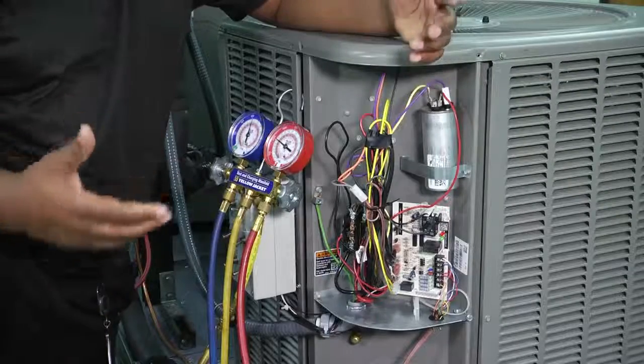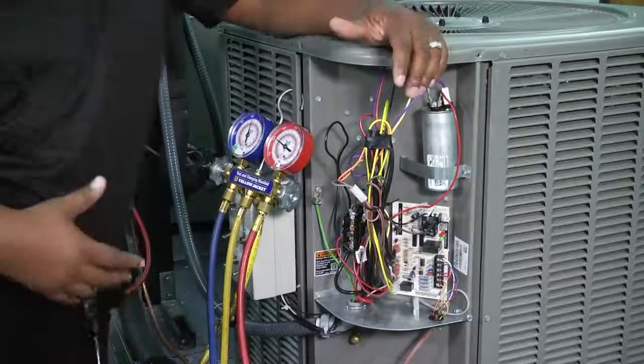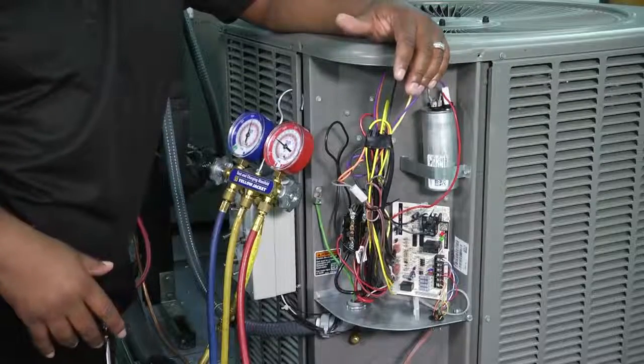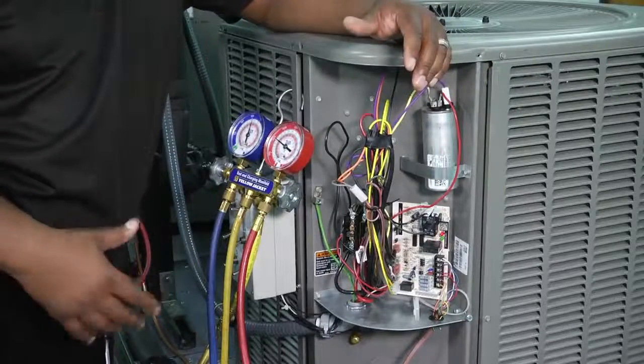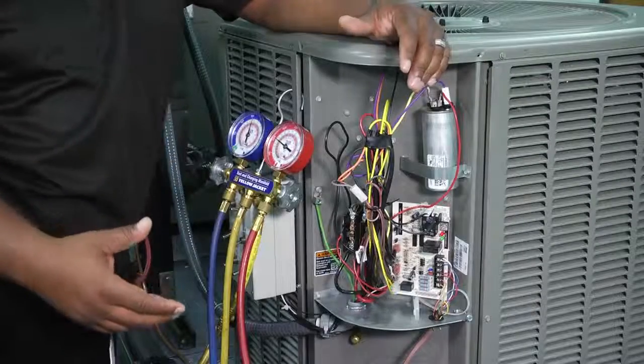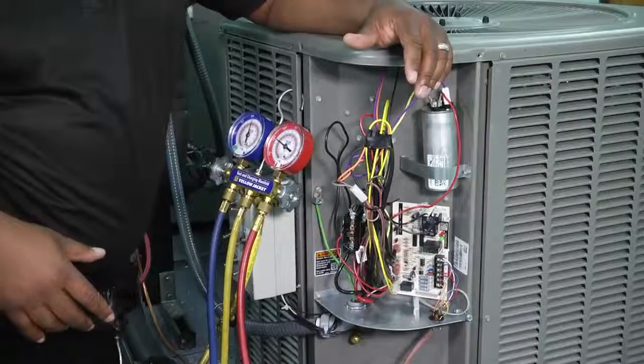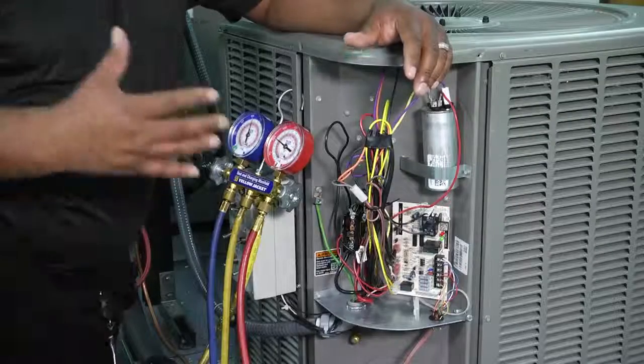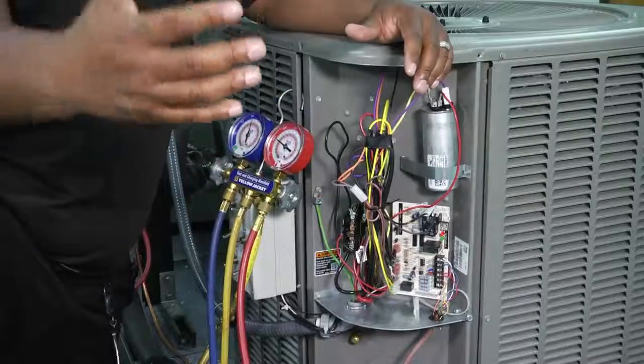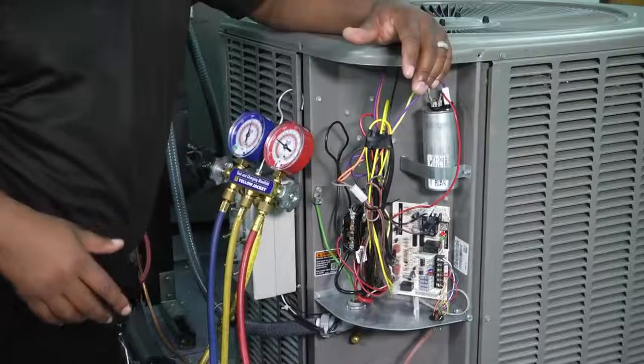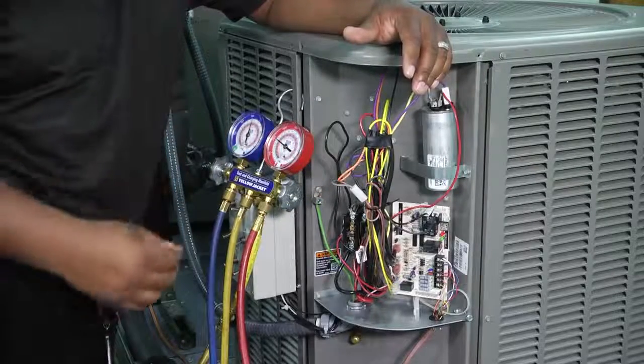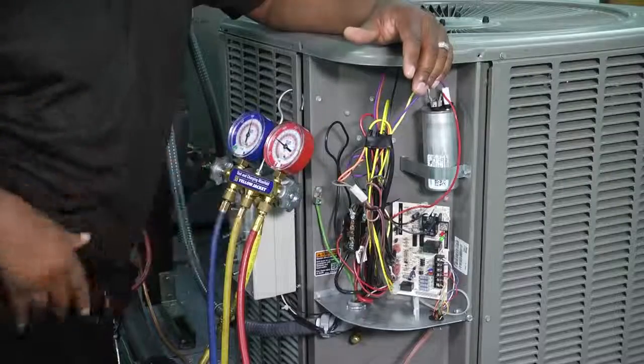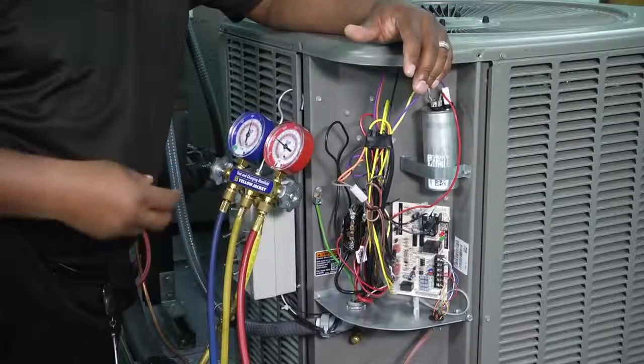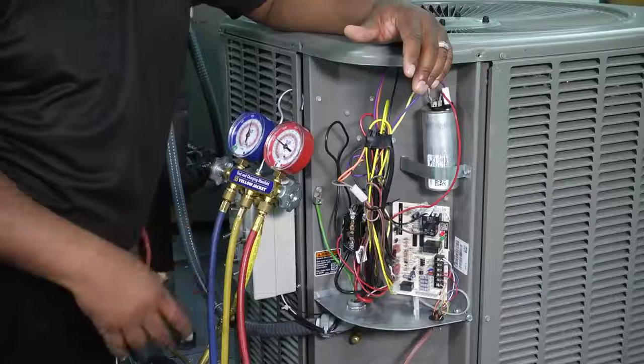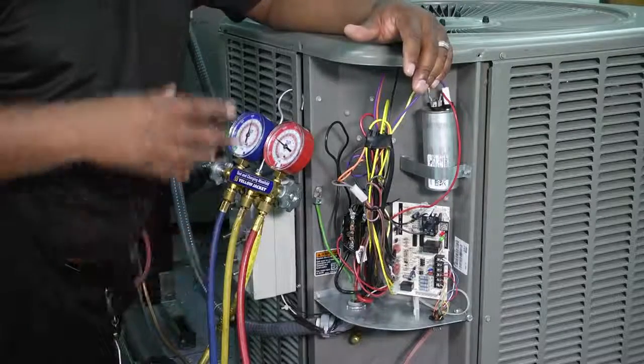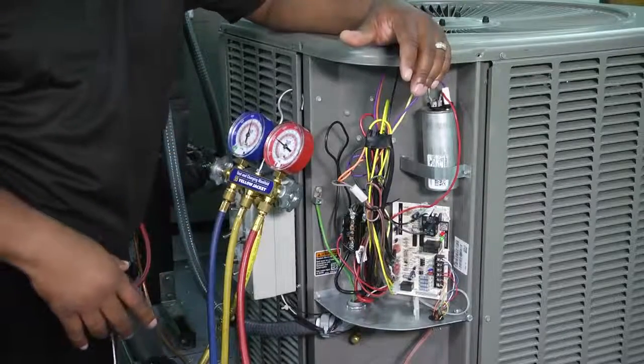Well, let's talk about the cleaning part. The first thing that we want to do is check all around the outside and the exterior of the condenser unit to make sure that there's no grass, no leaves, no debris that may have gotten caught up in the fins and different things like that. All of that stuff can actually prevent and restrict airflow that is coming across that coil. We need the airflow to be uninhibited as it passes across the coil. That's because that's a major part of our condensing process and our condenser's ability to go ahead and then reject heat out of the top.